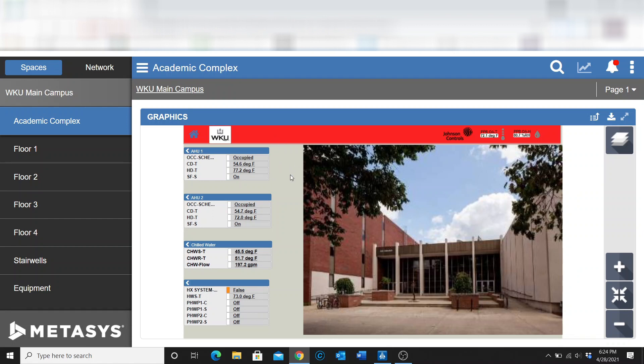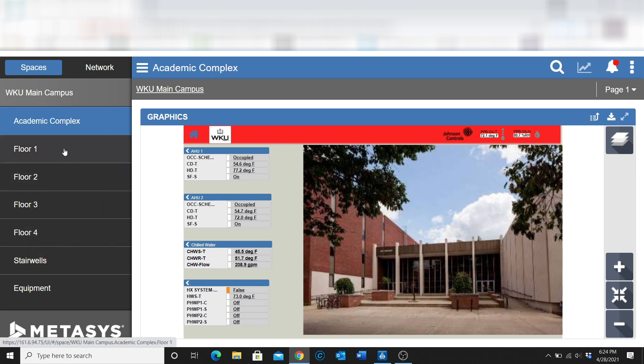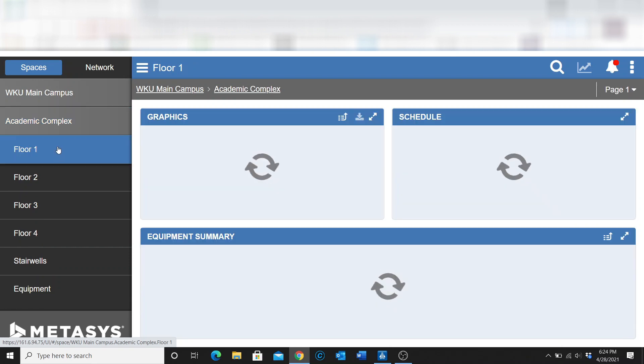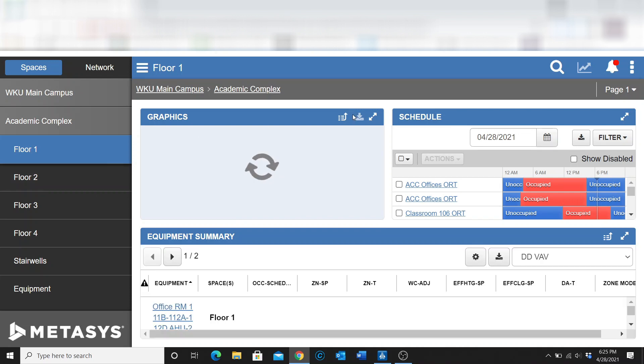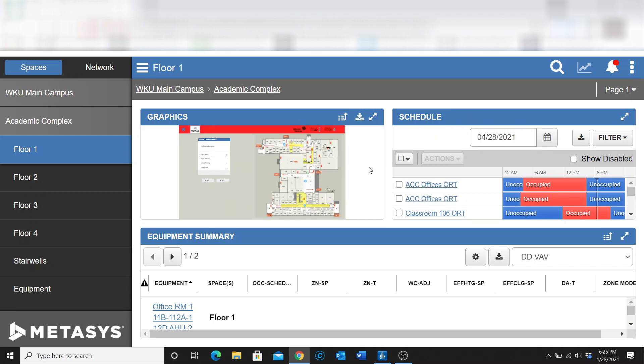From this one screen, I can tell what the air handler is doing, whether or not it's running, and see what the discharge temp is. I can also see what our chilled water is doing and what the hot water system is doing as well. Everything in MUI is broken up into spaces. I'm going to click on the first floor here and you will see some of the things I'm talking about — you can see the way we currently have this set up.